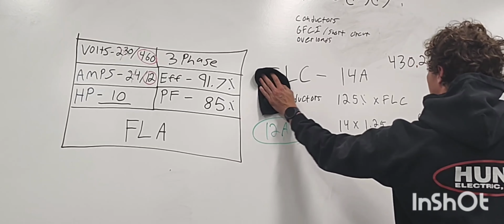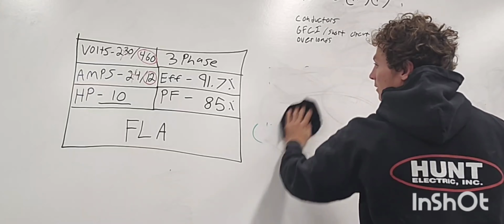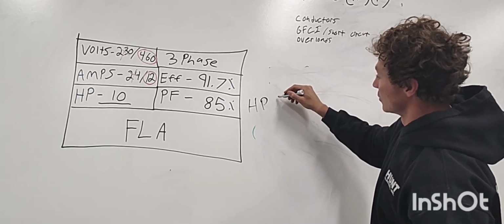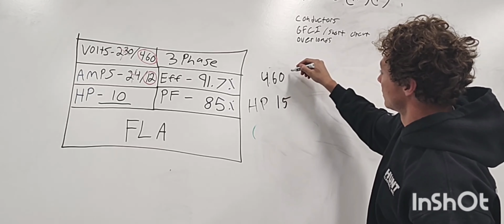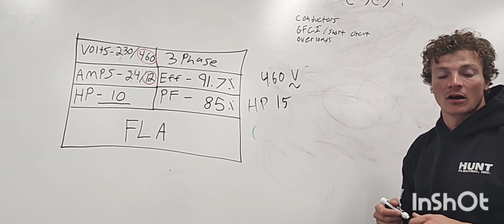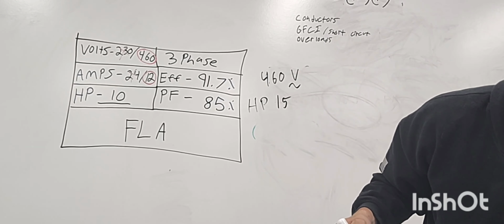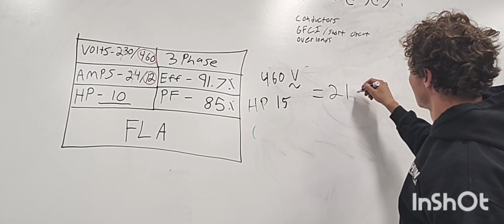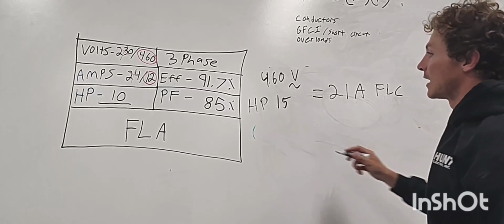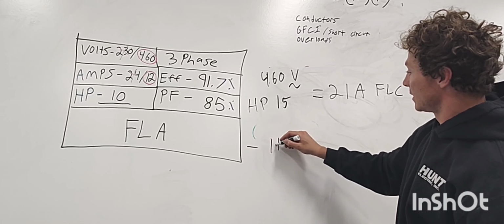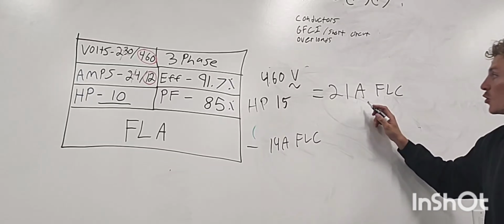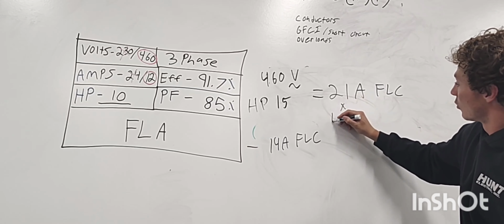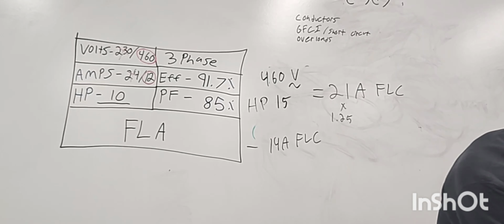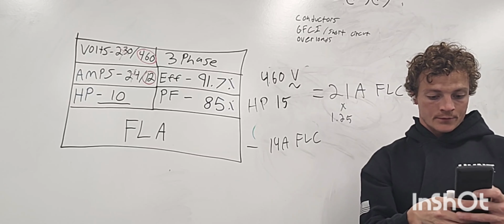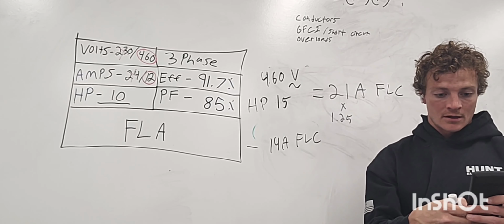So essentially, what we would then do is, if we had horsepower of 15, 460 volts, what did we get? 15, 21 amps FLC. And then that one was 14 amps, 14 amps FLC. We would go 21 times 1.25, and that is 21 times 1.25, 26.25.